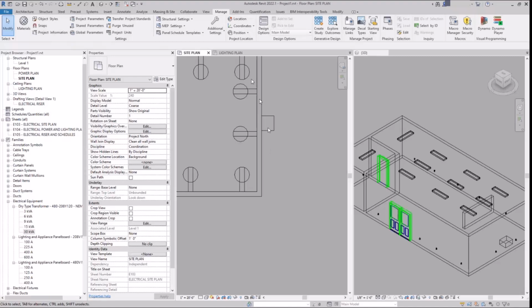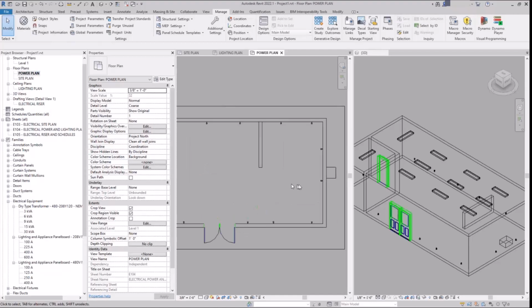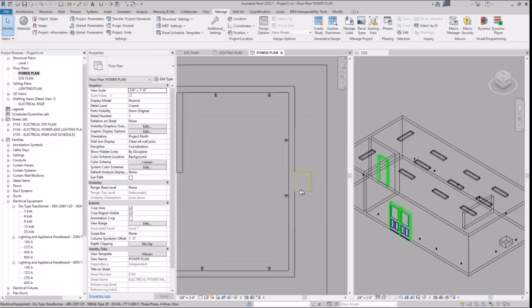A couple of things. Let's do some math because I like math. Here we go. This is what I was looking for. If I've got a 30 kVA transformer, 3-phase, how many amps on the 480 side can this thing handle? You said 30 kVA and the voltage is 277? 480 on the primary.